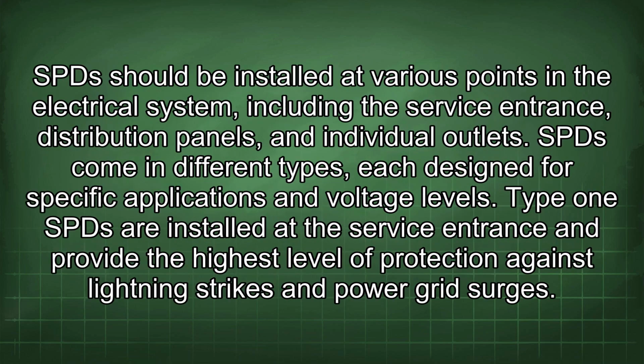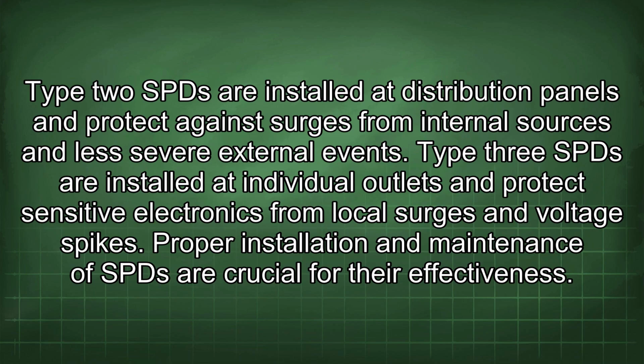SPDs should be installed at various points in the electrical system, including the service entrance, distribution panels, and individual outlets. SPDs come in different types, each designed for specific applications and voltage levels. Type 1 SPDs are installed at the service entrance and provide the highest level of protection against lightning strikes and power grid surges. Type 2 SPDs are installed at distribution panels and protect against surges from internal sources and less severe external events. Type 3 SPDs are installed at individual outlets and protect sensitive electronics from local surges and voltage spikes.